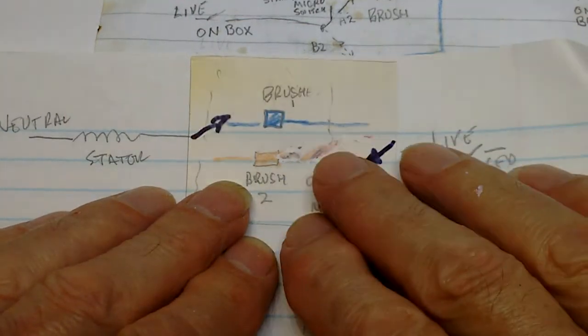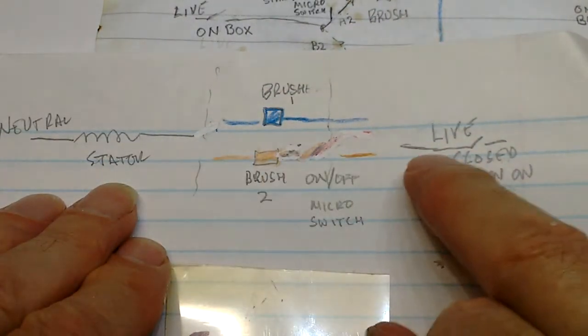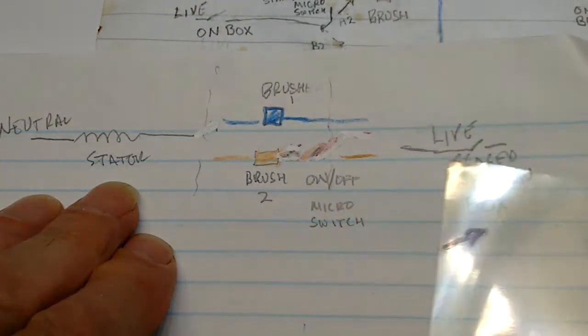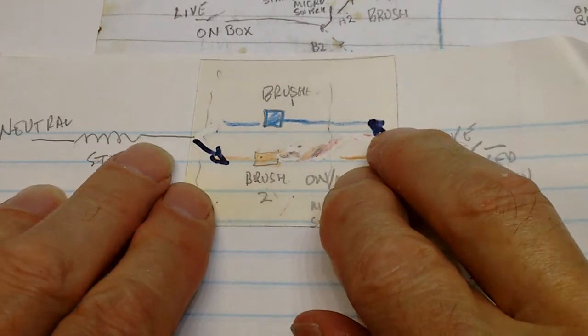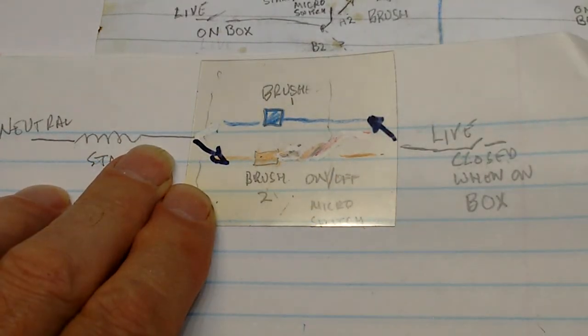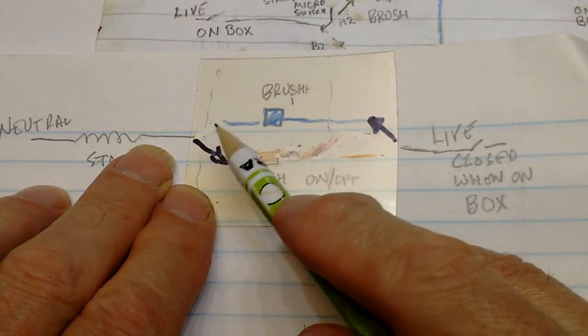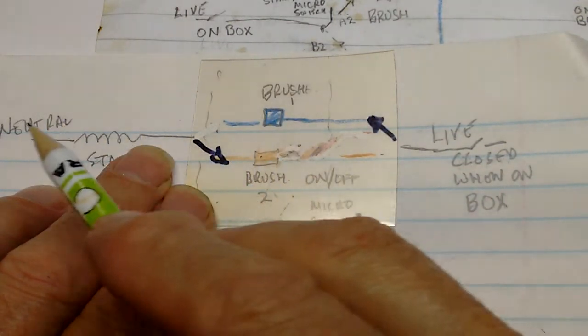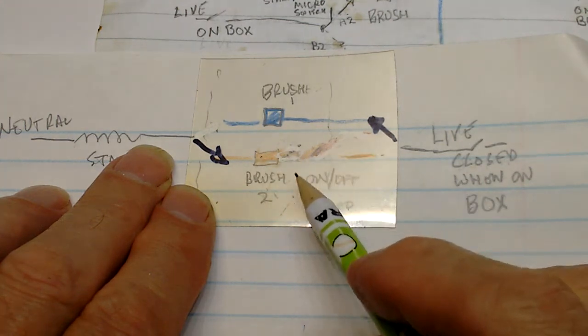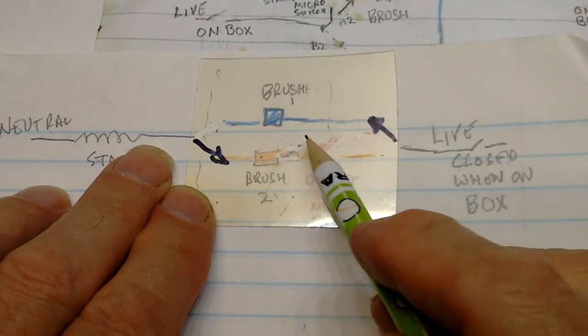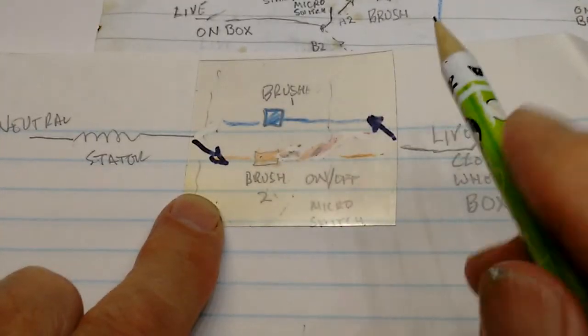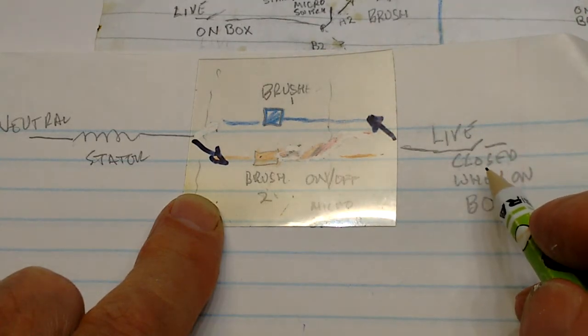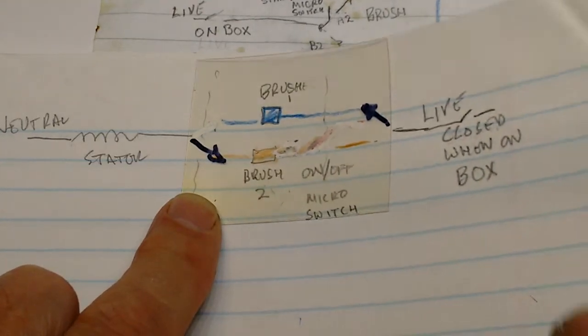If we put it in the middle position, then it's like that. The neutral doesn't connect to anything, live doesn't connect to anything. But if we put it in the reverse position, then the live comes up into the blue brush which isn't connected at this end, and the neutral comes in down to the brown brush which this switch then isn't connected. There's no connection at this end so this just doesn't operate. So in reverse then it operates all the time provided it's on the box, on its collection box. So that essentially is how it works.